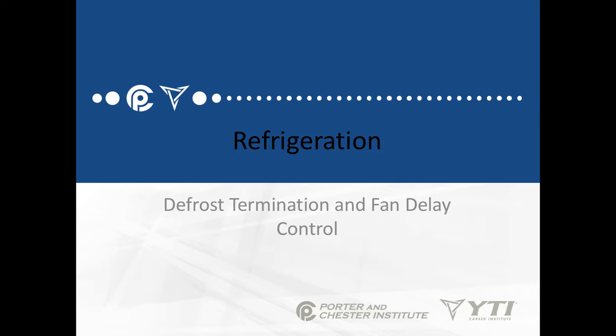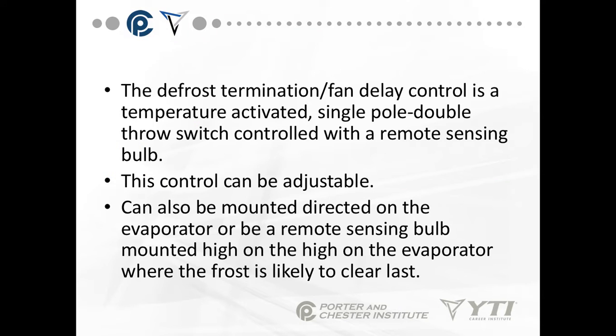In this video, we're going to talk about defrost termination and fan delay. The whole purpose of defrost termination and fan delay is that we need to be able to take the system out of defrost so that we're no longer putting heat into the box once the ice is melted. The whole purpose of defrost is to melt the ice off the evaporator, so once the ice is melted, there's no point keeping the system adding heat to a cool environment.